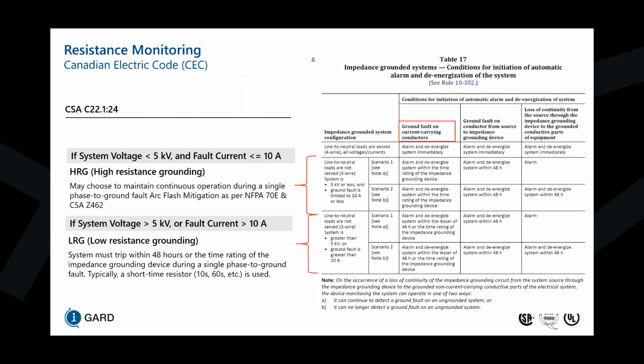So when we talk about table 17, we look at row 2 as high resistance grounding, where the system voltage is below 5 kV and fault current is less than or equal to 10 amps. High resistance grounding's main benefit is to maintain operation during a single phase to ground fault while satisfying arc flash mitigation as per NFPA 70E and CSA Z462.